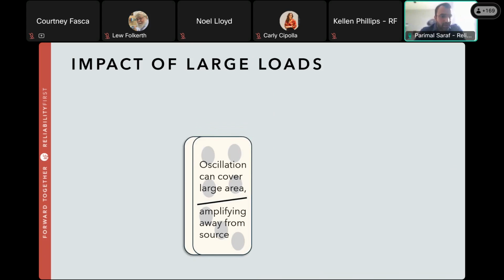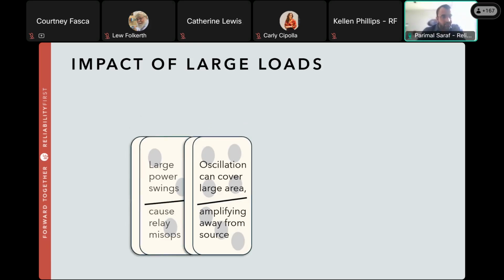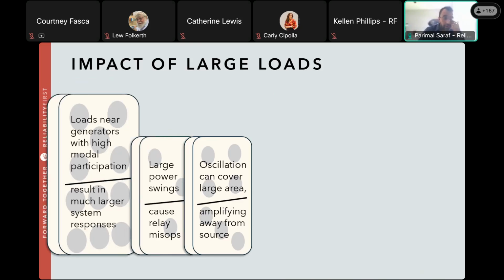Can you click, Courtney, to have all the three? So once more, the way large loads impact oscillatory stability is, as I mentioned, through forced oscillations. And if these large loads are closer to generators that have a high modal participation in an inter-area mode, these large loads can amplify those inter-area oscillations and destabilize the electric grid. These large power swings resulting from these ramp up, ramp down profiles can also cause relay misoperations, which in turn can trigger cascading in the system and again cause a major instability event in the electric grid. And also these oscillations can cover a large area, as is well known.